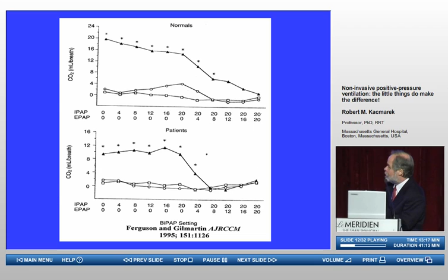Here you see normals or patients. This is with the typical single orifice expiratory port in the system, and both of them show significant CO2 rebreathing. When isolation valves were added or when actual exhalation valves were added to the system, the CO2 rebreathing was eliminated. The other factor that eliminated it was adding PEEP to the system. Now, almost all of these ventilators on the market today do not allow you to set them at 0 centimeters of water PEEP. You may go to the minimum level, but if you actually measure what's going on, they maintain 3 or 4 centimeters of water positive end expiratory pressure, even at their lowest setting. The reason for that is to avoid CO2 rebreathing, to allow a consistent flow towards the patient during the expiratory phase so you don't get retrograde movement of exhaled gas and you don't see CO2 rebreathing. So always consider this a possibility in patients that are difficult to ventilate unless you have 5 or 6 centimeters of water PEEP applied to the system.